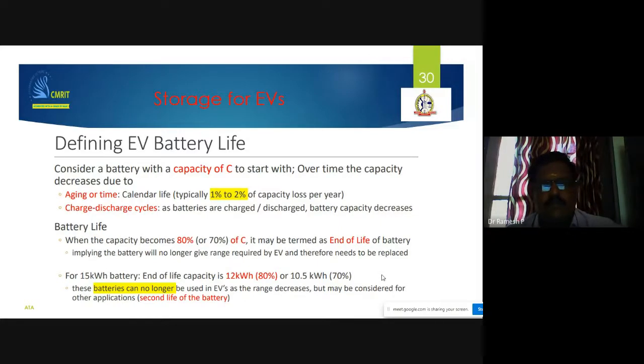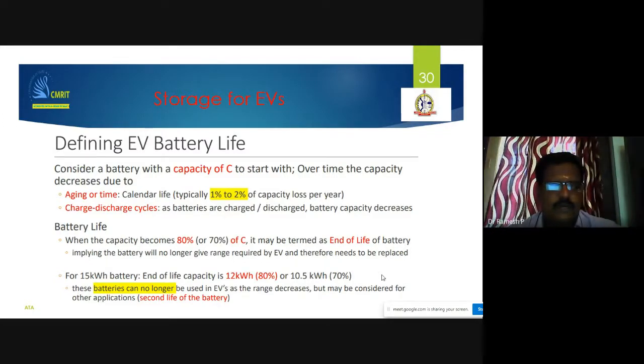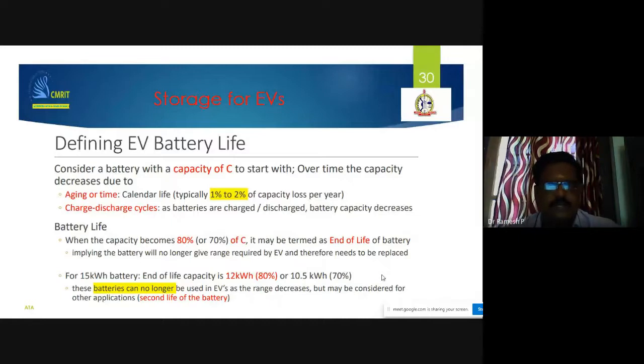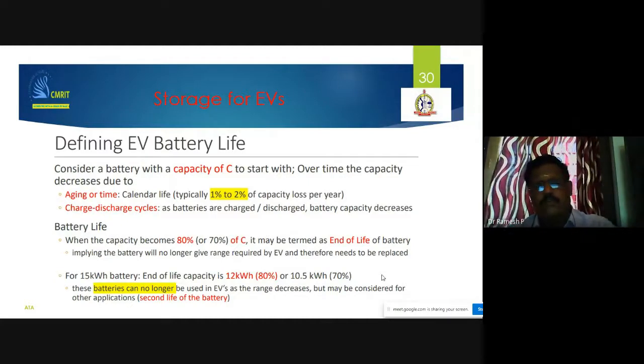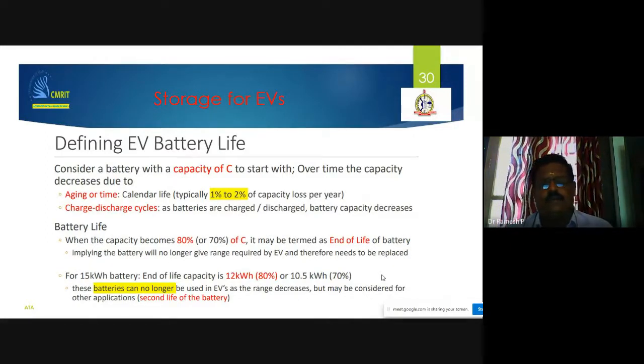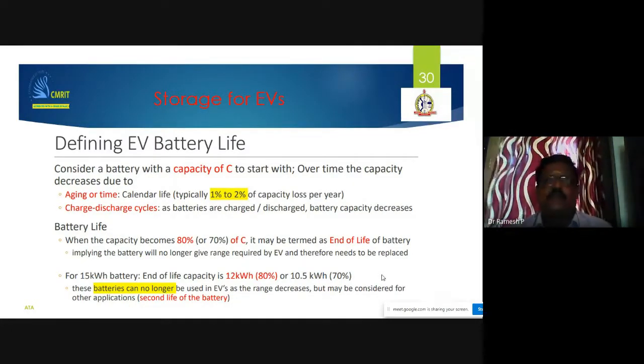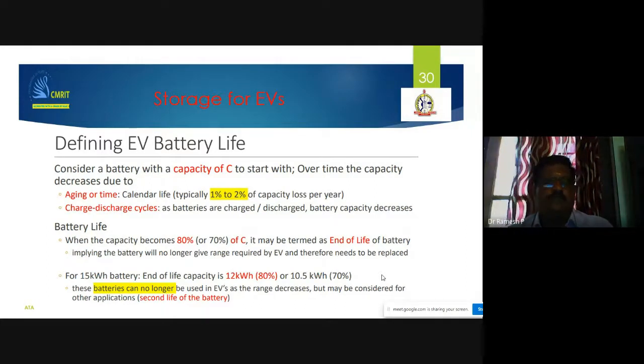This type of battery is not suitable for electric vehicle use. For example, here's one: a 15 kilowatt battery, where end of life capacity is 12 kilowatt-hour, that is 80%; at 70% it's 10.5 kilowatt-hour. When battery capacity reduces to 12 kilowatt-hour or 10.5 kilowatt-hour, that battery is not suitable for electric vehicles anymore. That battery is used for a second life purpose, such as UPS or other storage device applications, not for electric vehicles.